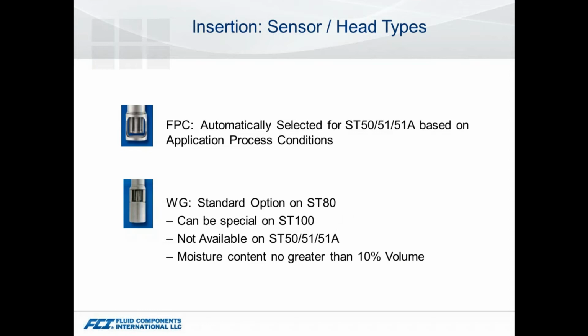Again, we want to look at the wet gas sensors are really not suited for dual phase. So we're looking at things that are lower moisture content. Maybe you've got entrained moisture in the 5% area. Nothing to exceed 10%. Above that, it's really a dual phase measurement, which thermal should probably not be considered as a solution.